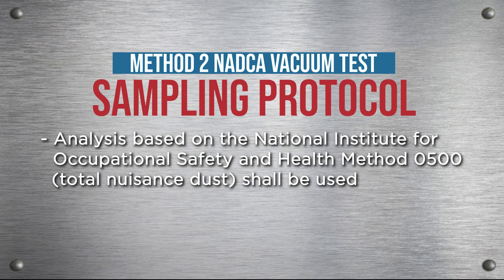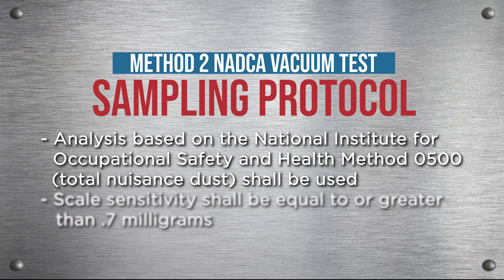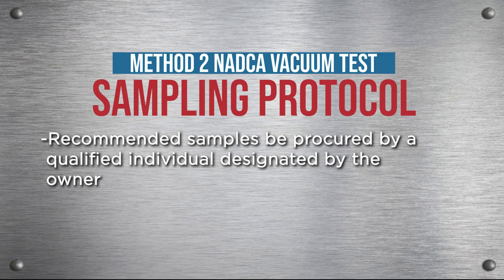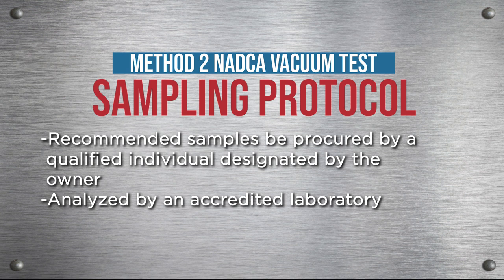Analysis based on the National Institute for Occupational Safety and Health Method 0500, total nuisance dust, shall be used. Scale sensitivity shall be equal to or greater than 0.7 milligrams and shall be calibrated in accordance with the manufacturer's written recommendations. Generally, samples are sent to a laboratory for testing. However, sampling equipment is capable of being brought onto the worksite. It is recommended that samples be procured by a qualified individual designated by the owner and analyzed by an accredited laboratory.